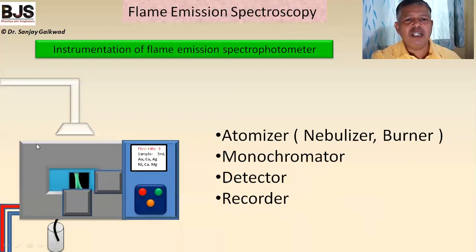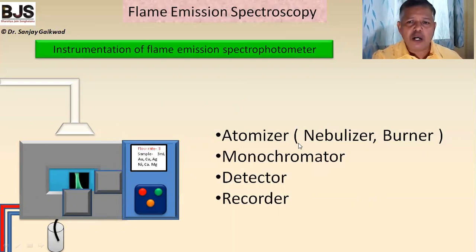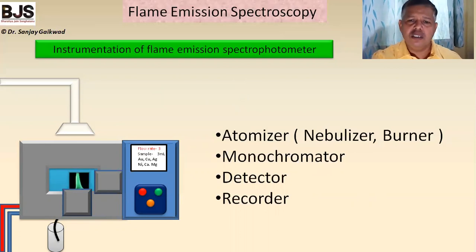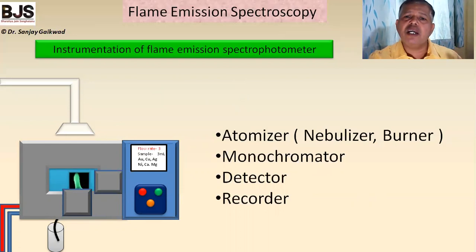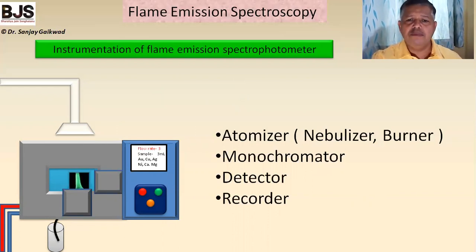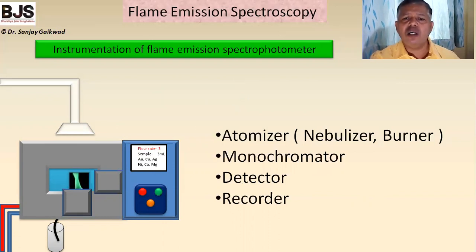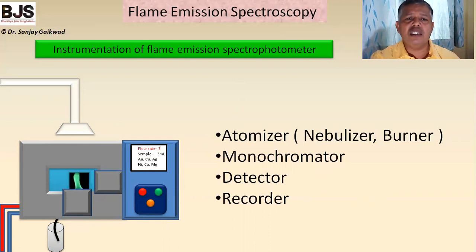The instrumentation is very similar to AAS, but instead of AAS there is no lamp here. The parts are: an atomizer containing the nebulizer and burner; a monochromator which may be a prism, grating, or simple filters — for example, to determine calcium we require a calcium filter; a detector such as a phototube, photovoltaic cell, or photomultiplier tube; and a recorder that directly records the intensity and wavelength of the emitted light.